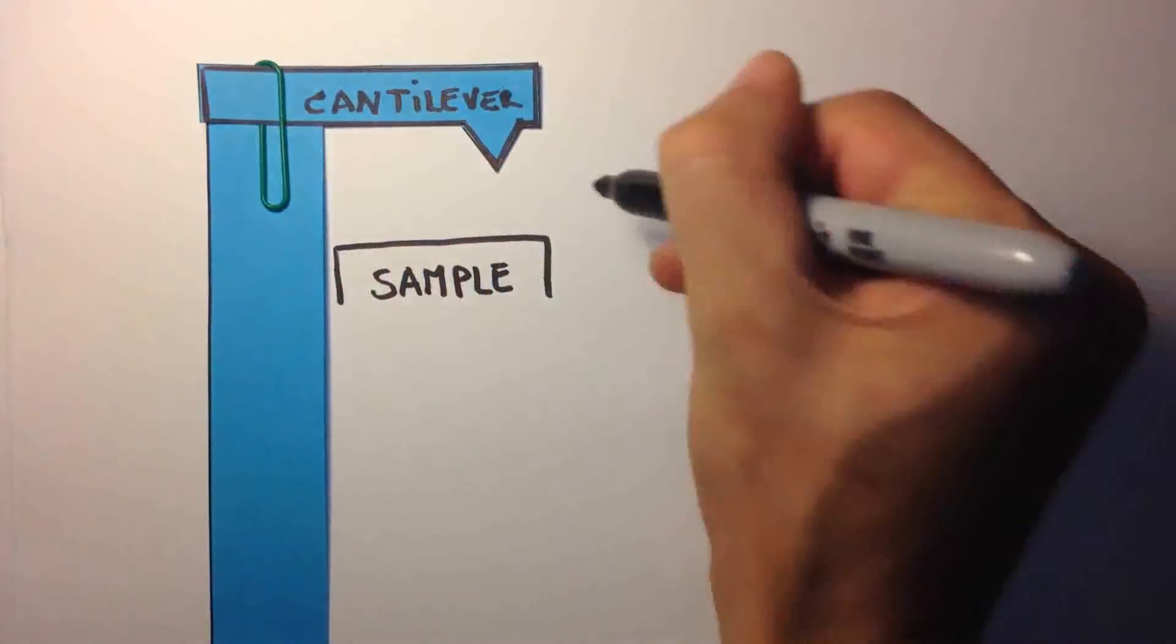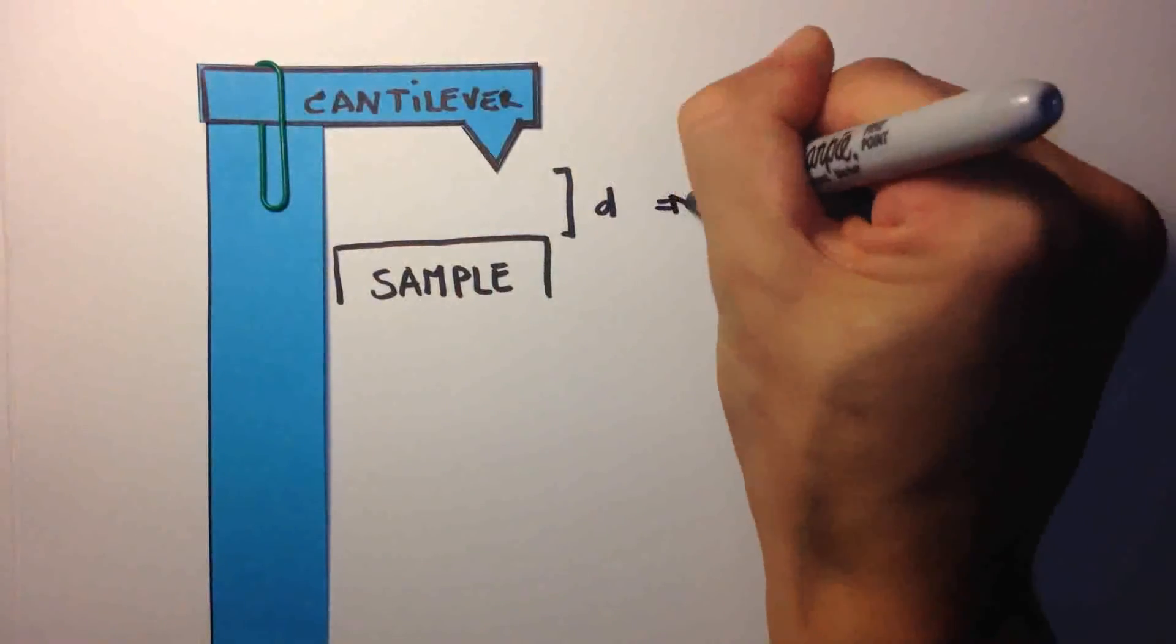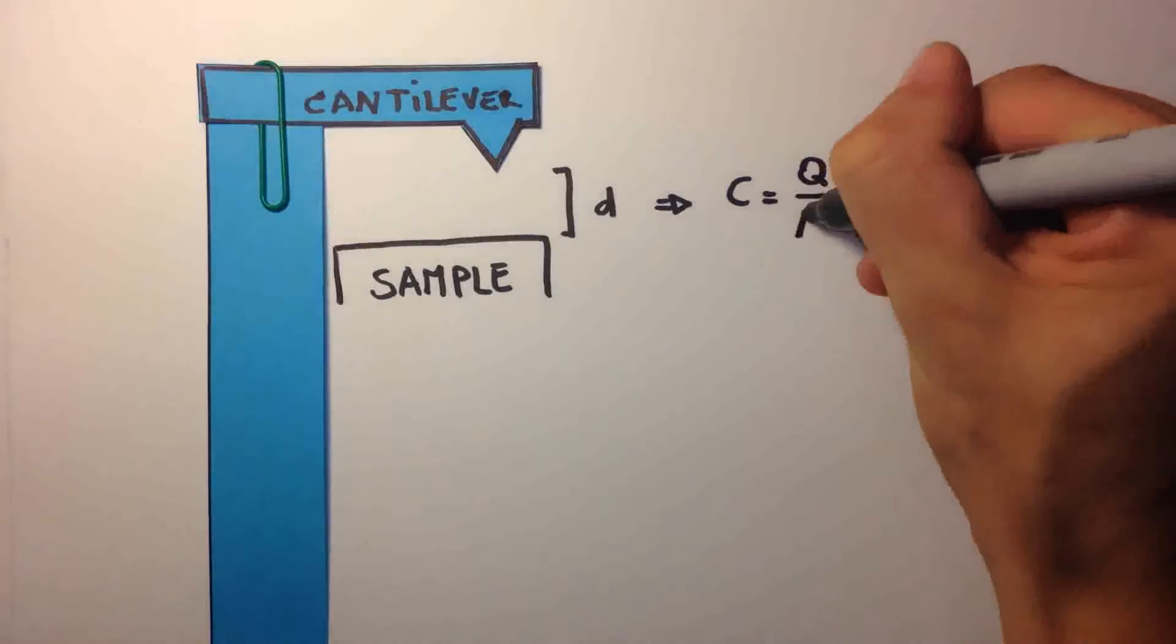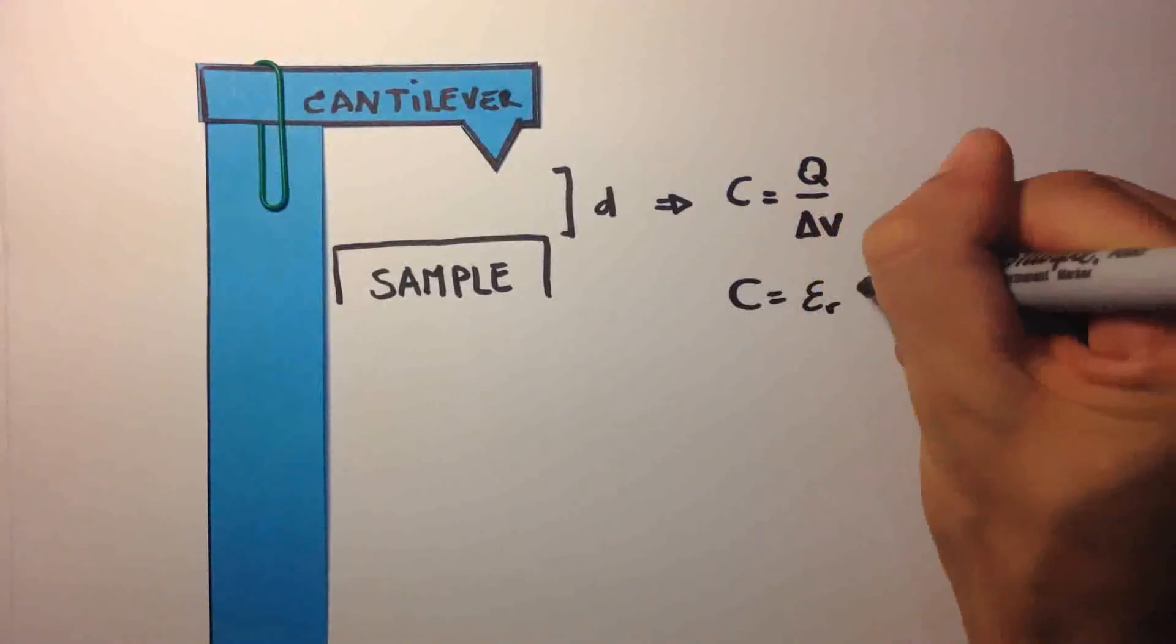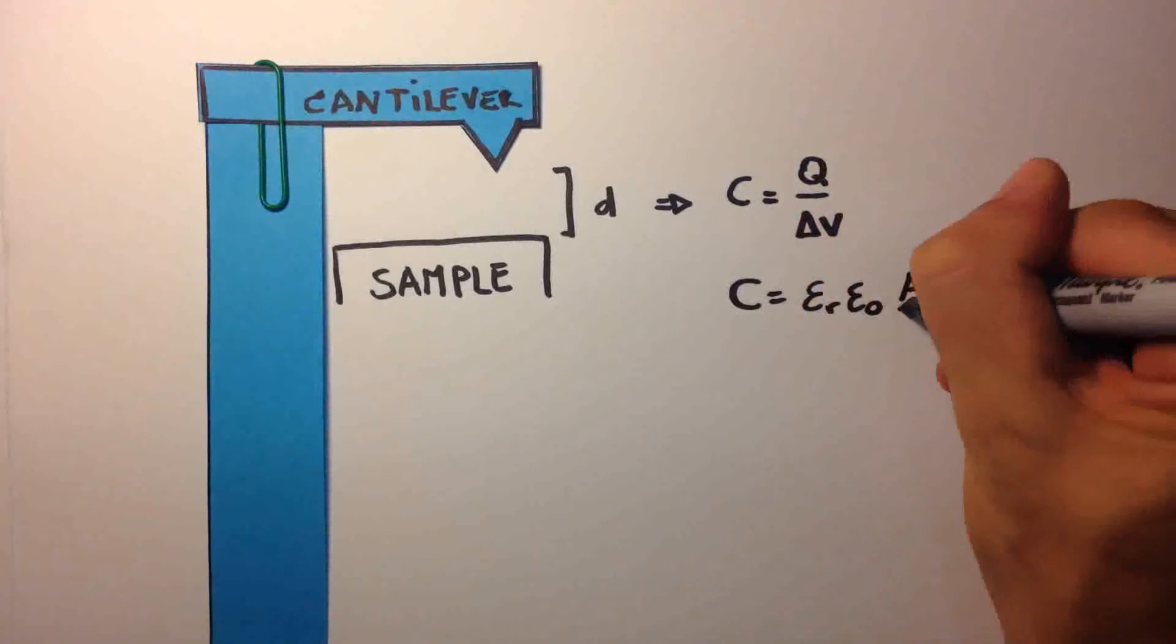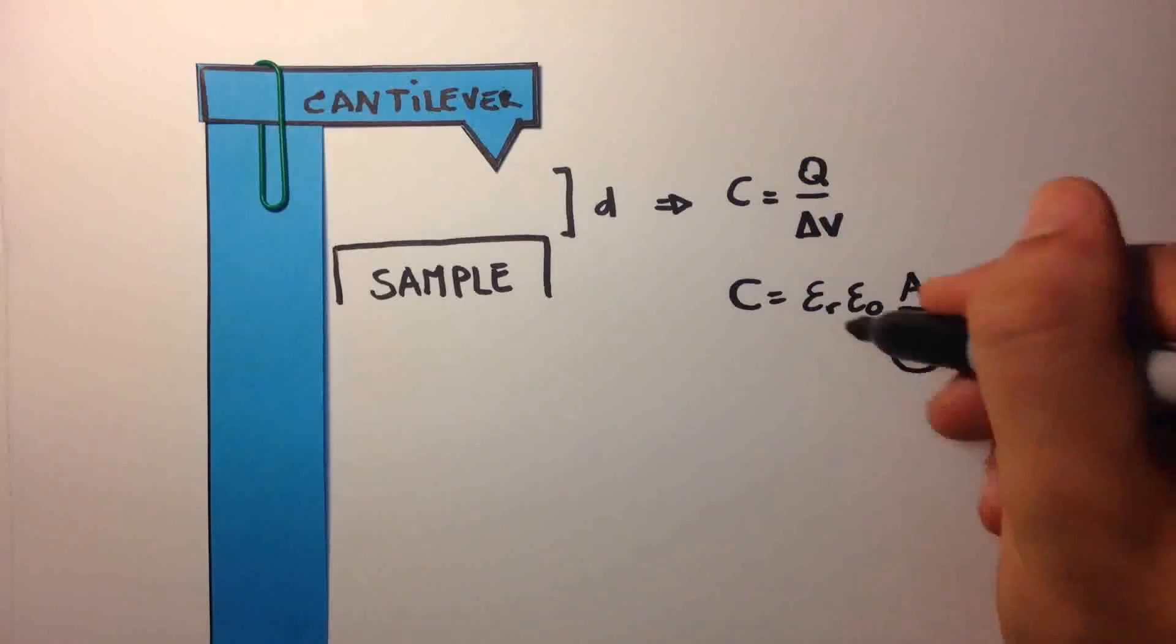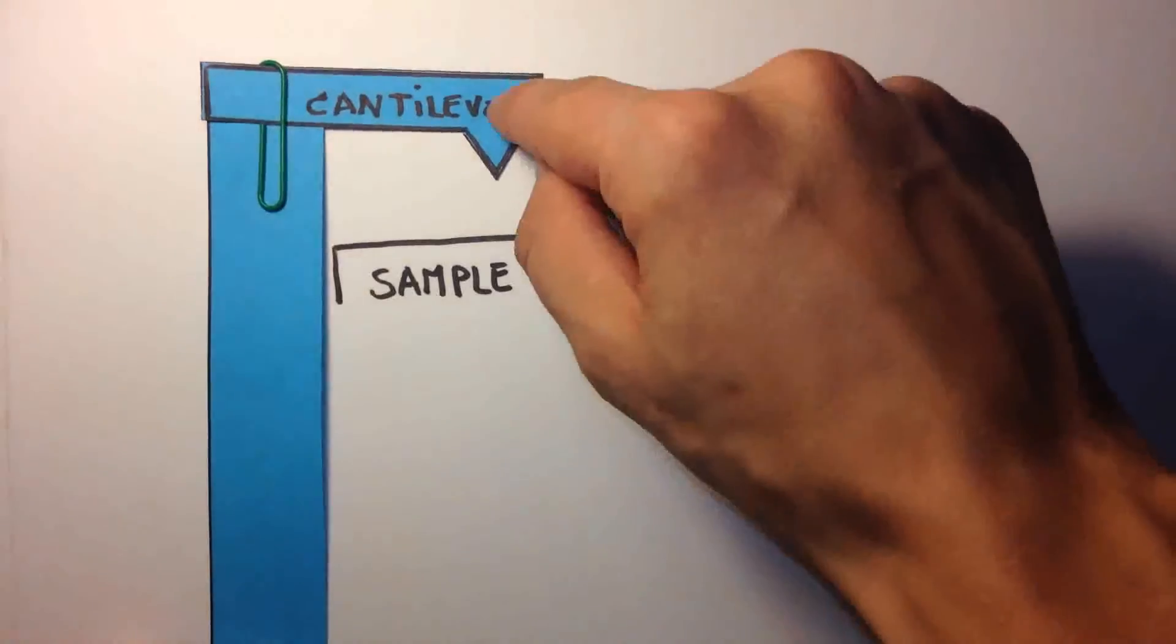When the cantilever and the sample are not in contact, the system acts like a capacitor. The capacitance is equal to the ratio between the amount of charges and a potential difference. In addition, it is also inversely proportional to the distance between the tip and the sample. Therefore, changing this distance will in turn change the value of the capacitance. And this is precisely what happens in a Kelvin probe microscope.